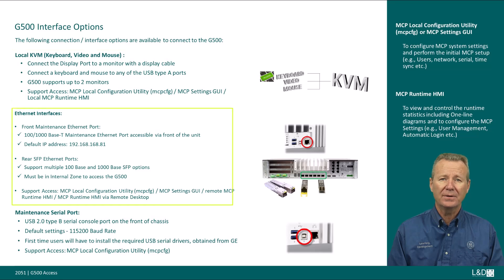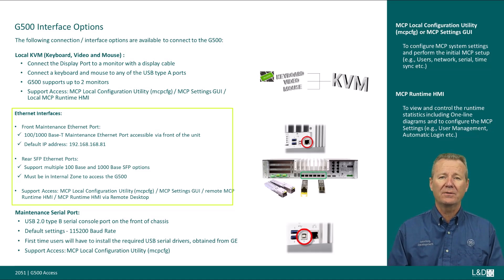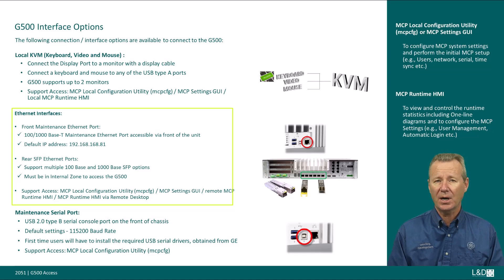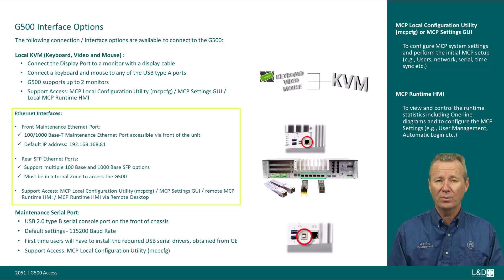Two, Ethernet interfaces include a front maintenance Ethernet port and rear SFP Ethernet ports. The front maintenance Ethernet port is a 100/1000 base T port accessible via the front of the unit, with a default IP address of 192.168.168.81. For rear SFP Ethernet ports, there is support for multiple 100 base and 1000 base SFP options. You must be in the internal zone to access the G500. For support access: MCP local configuration utility, MCP CFG, MCP settings GUI, remote runtime HMI, and MCP runtime HMI via remote desktop.